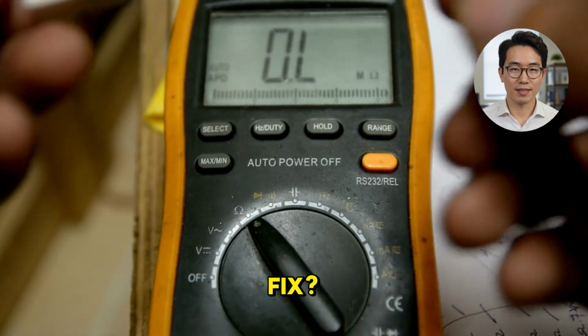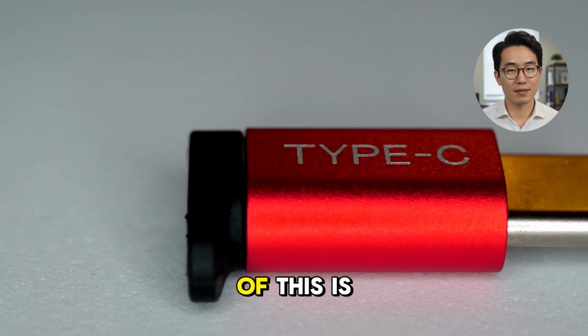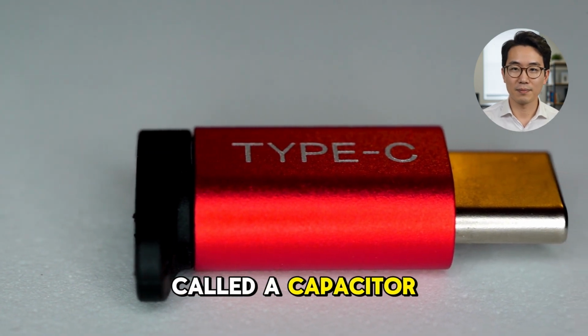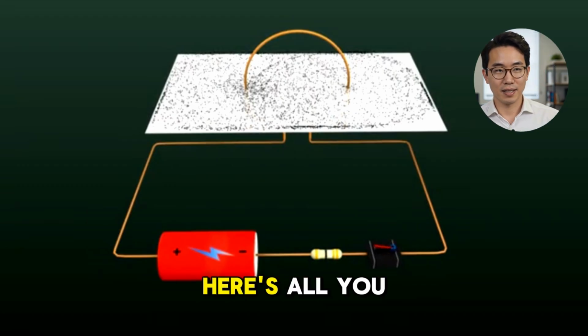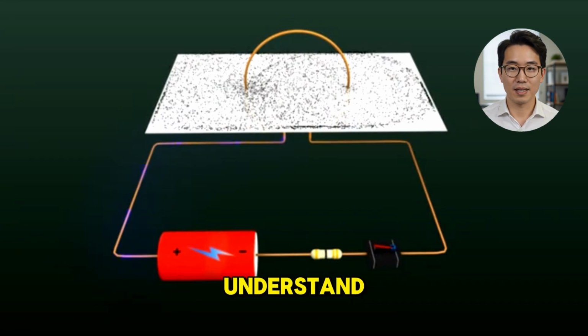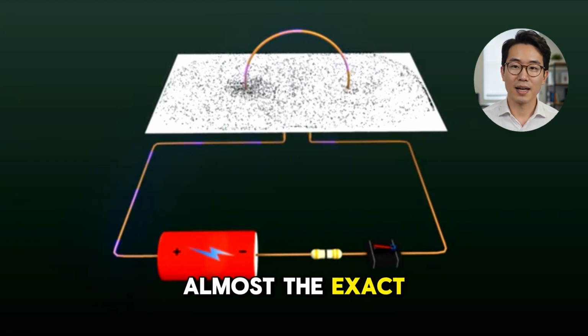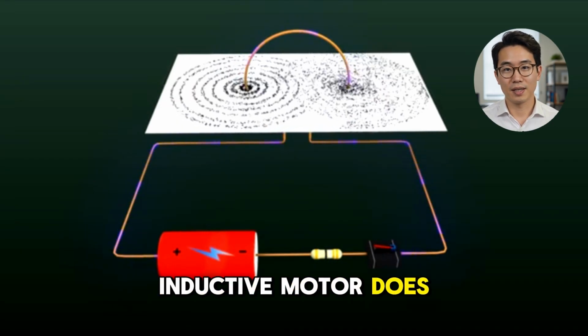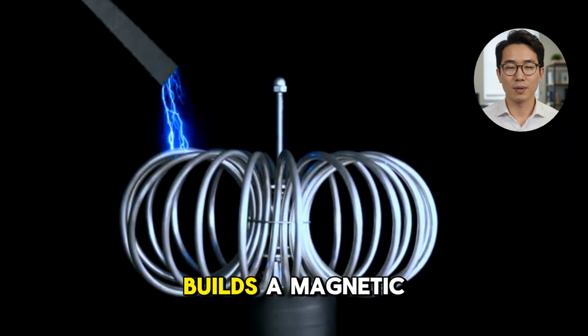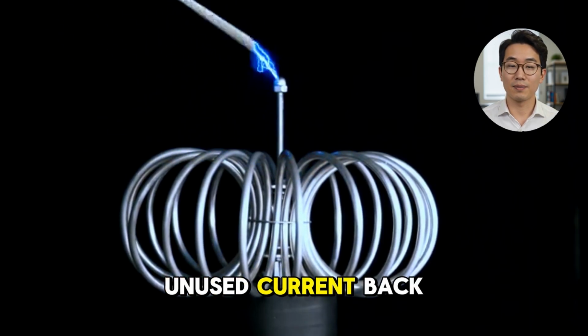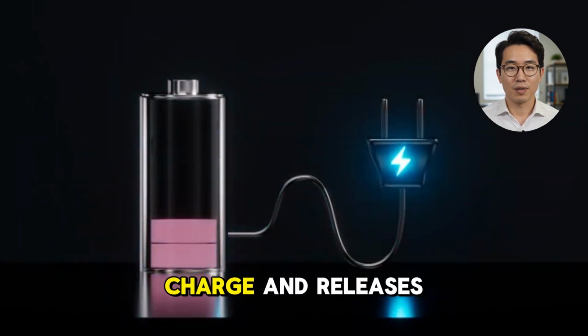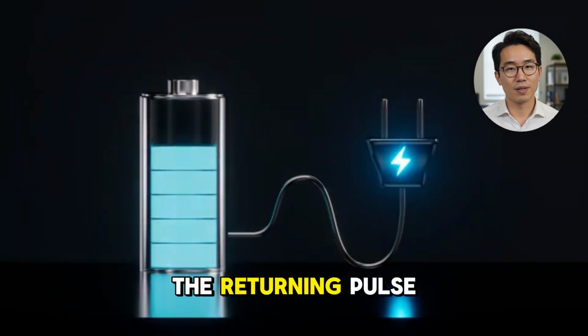So what's the fix? The device at the center of this is called a capacitor. Before you skip past the technical term, here's all you actually need to understand. A capacitor does almost the exact opposite of what an inductive motor does. A motor pulls in reactive current, builds a magnetic field, and sends the unused current back. A capacitor stores electrical charge and releases it in a way that counters the returning pulse.